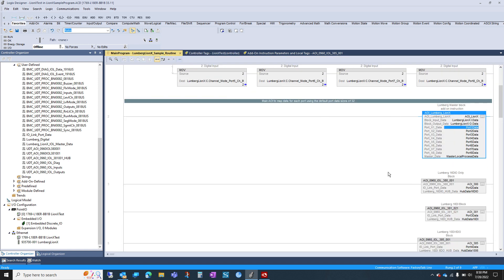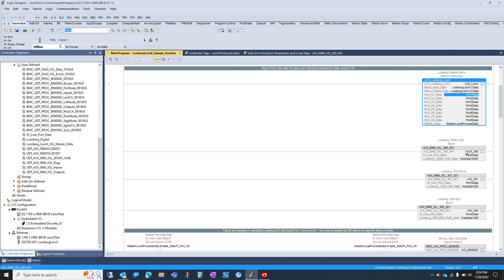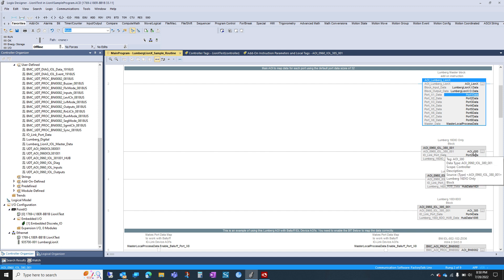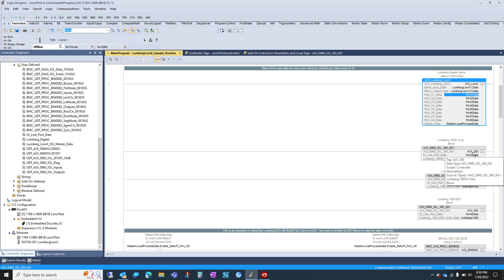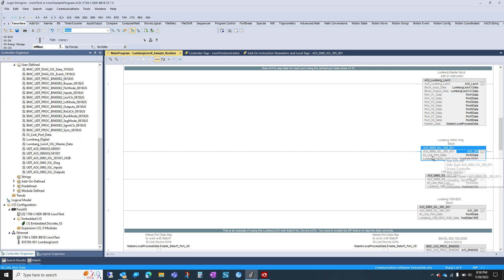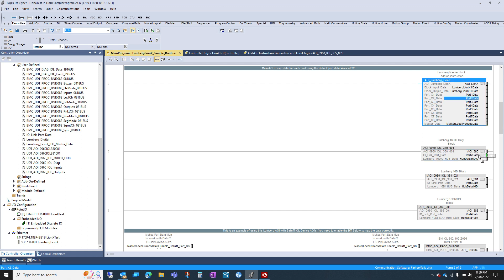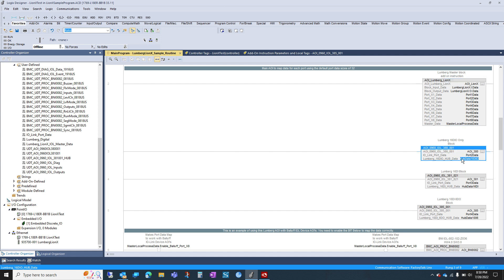If you do have an AOI like our Lumberg AOIs for our hubs, here's the three hub AOIs we have in here. You'll see this is the 16 digital input output hub. Again, I just named the AOI. The second section is the port number. So this is this tag. So if I'm plugged into port 2, I move it here. And then this is my data for that hub.